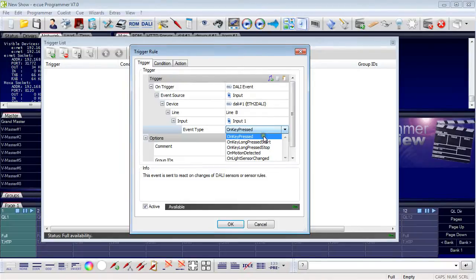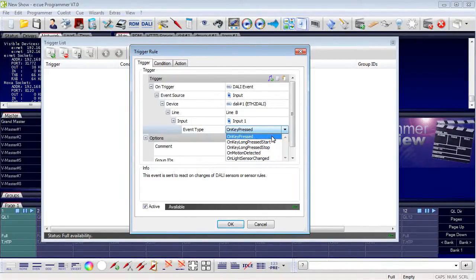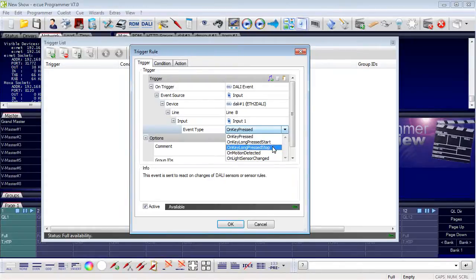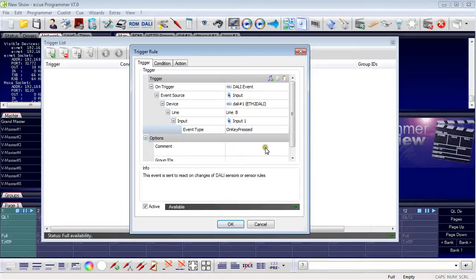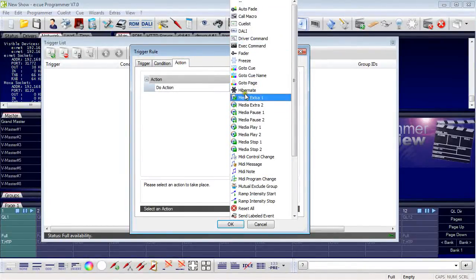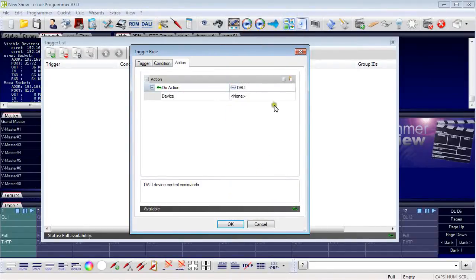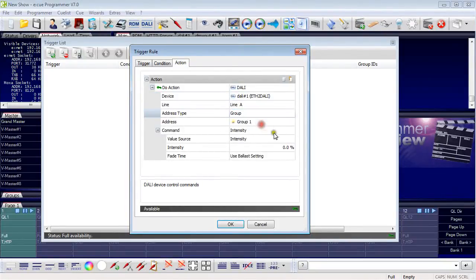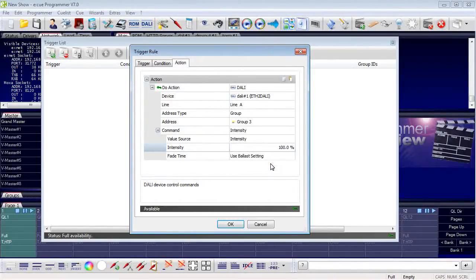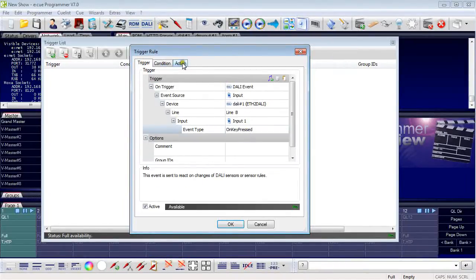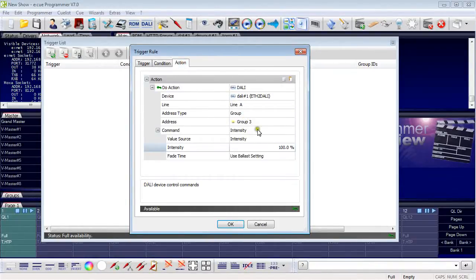In the field Event Type, you can select pressed, long pressed start, and long pressed stop. If you press the button for less than a second, you get on key pressed. If you keep the button pressed for longer than a second, you get a long pressed start, and when you release, you get a long pressed stop. I use just the simple way. For the action, I take a DALI command on Ethernet to DALI, using a group — group 3 of fixtures — with the intensity command set to 100%. The trigger is the input, a simple press, and the executed action is setting intensity in a group to 100%.